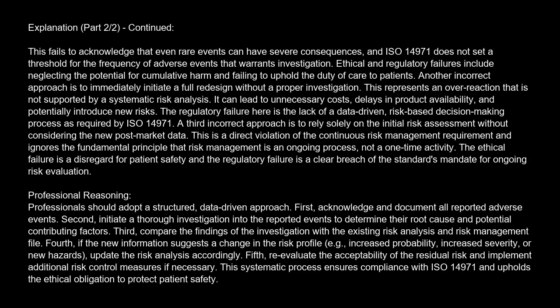Professional reasoning. Professionals should adopt a structured, data-driven approach. First, acknowledge and document all reported adverse events. Second, initiate a thorough investigation into the reported events to determine their root cause and potential contributing factors. Third, compare the findings of the investigation with the existing risk analysis and risk management file. Fourth, if the new information suggests a change in the risk profile, e.g., increased probability, increased severity, or new hazards, update the risk analysis accordingly. Fifth, reevaluate the acceptability of the residual risk and implement additional risk control measures if necessary. This systematic process ensures compliance with ISO 14971 and upholds the ethical obligation to protect patient safety.